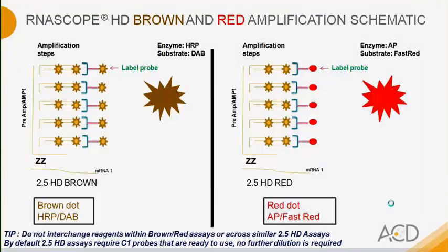This slide highlights the amplification steps of the brown and red chromogenic assay. The amplification cascade starts with pre-amplifiers binding to the tail sequence of the ZZ probe pair, followed by amplifier and label probe binding. The label probe is conjugated with either the HRP or the AP enzyme. By reacting with DAB substrate or Fast Red substrate, a brown or red signal will be developed. So a few points to note here. We do not recommend interchanging reagents between the brown and red assay or across similar 2.5 HD assays. By default, the 2.5 HD assay requires C1 probe that is ready to use. No further dilution is required.